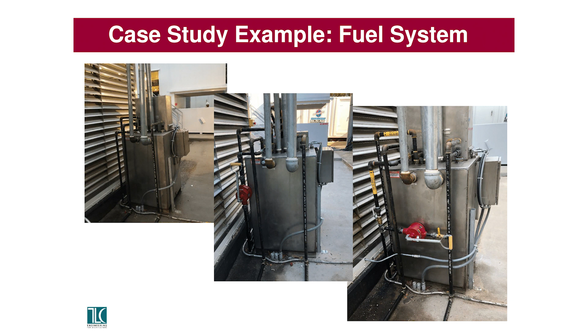In this particular example, this is a day tank, happens to be outside - that's not the important part. One of the requirements is for there to be a hand pump at the day tank, so that if the electric pump doesn't work, you can manually pump fuel. First thing I said when I got there was, hey, is there supposed to be a hand pump? Everybody looked at me like I had two heads, like they'd never heard of such a thing before.